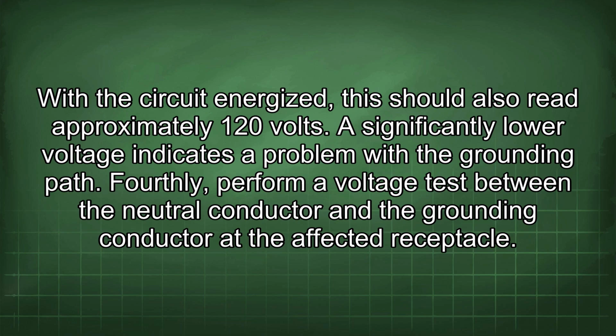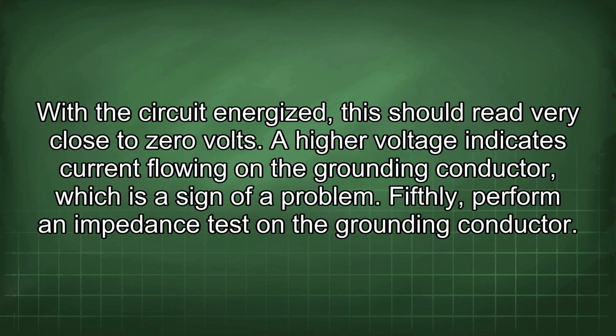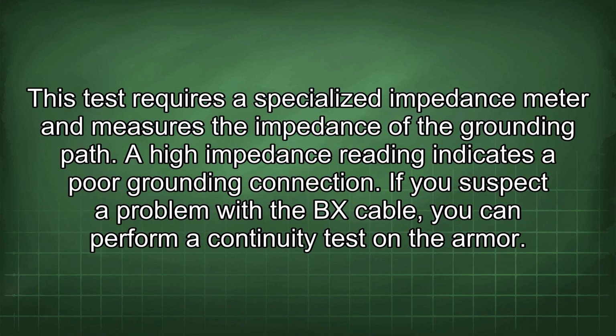Fourthly, perform a voltage test between the neutral conductor and the grounding conductor at the affected receptacle. With the circuit energized, this should read very close to 0 volts. A higher voltage indicates current flowing on the grounding conductor, which is a sign of a problem. Fifthly, perform an impedance test on the grounding conductor. This test requires a specialized impedance meter and measures the impedance of the grounding path. A high impedance reading indicates a poor grounding connection.